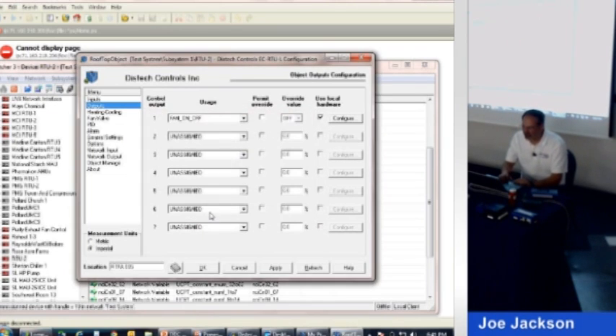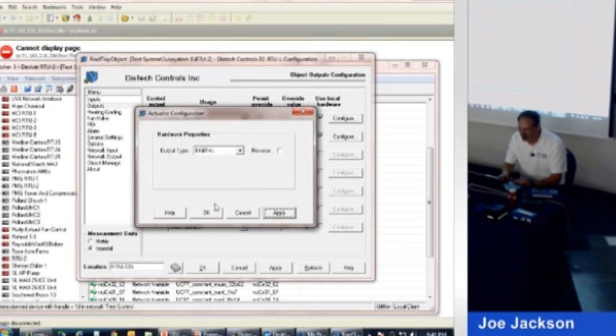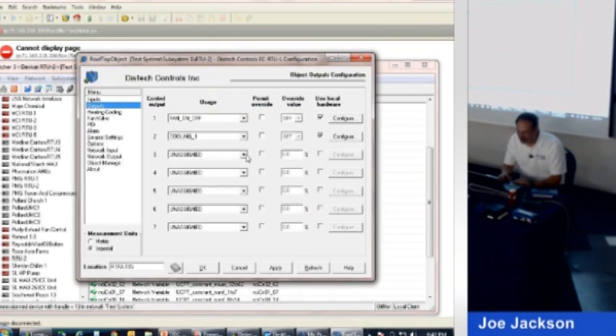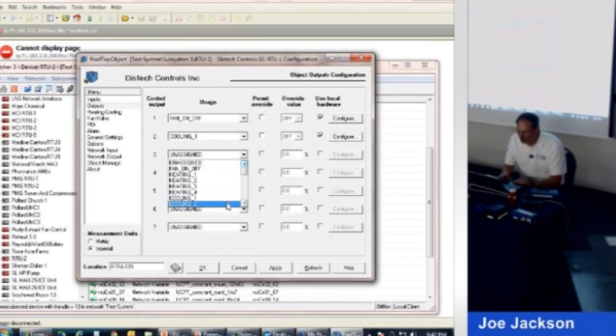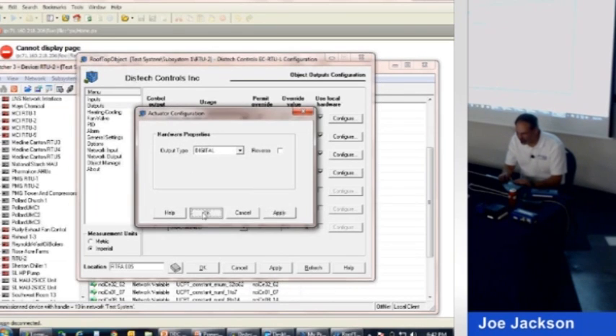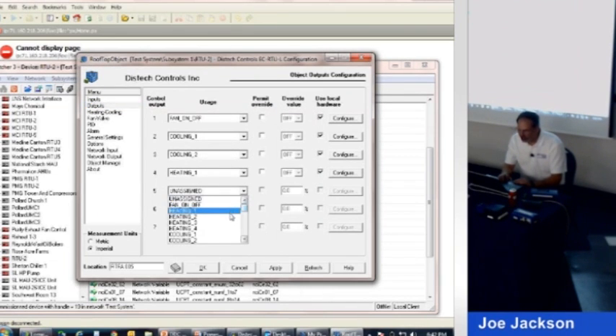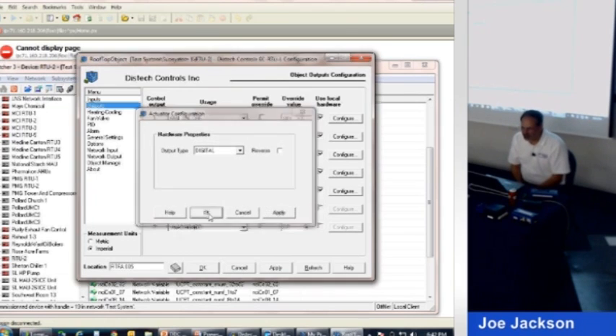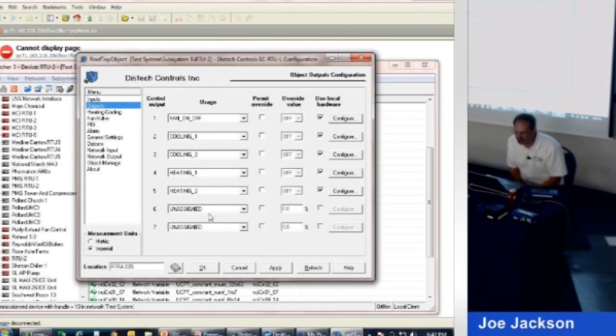What else do you have to turn on and off in a rooftop unit? Compressors. So we'll put cooling stage 1 there, and we'll put on cooling stage 2 there. And what else? Heating stage 1, gas valve, same thing, yep. So this is our standard. We've just developed a standard 2-stage heat, 2-stage cool rooftop.